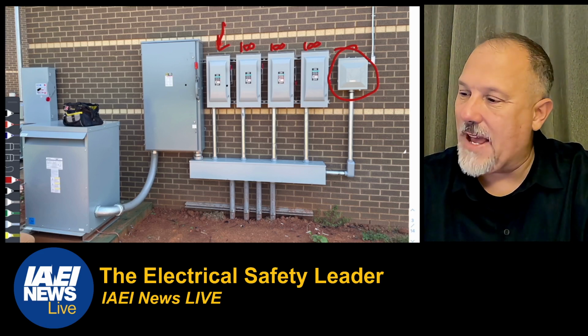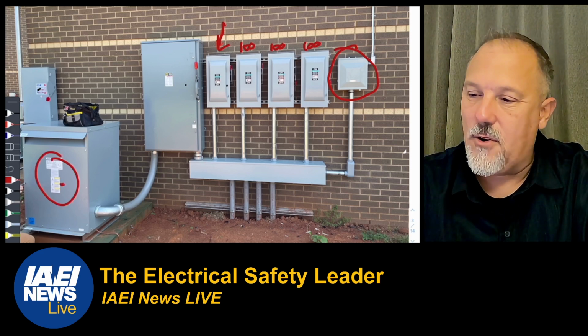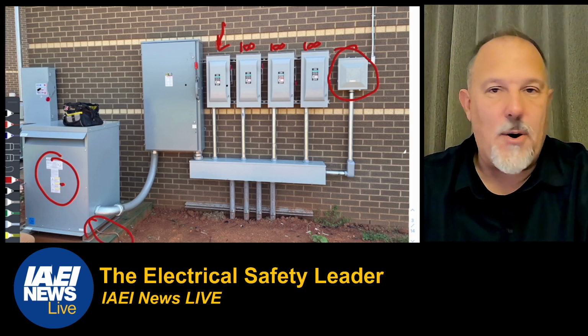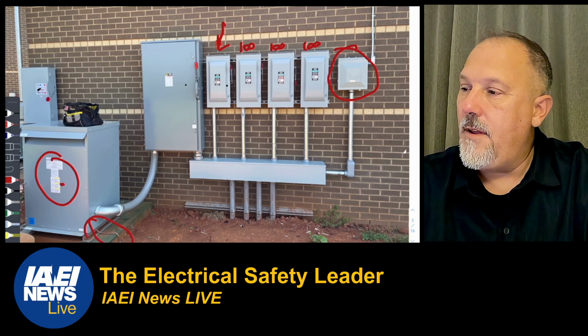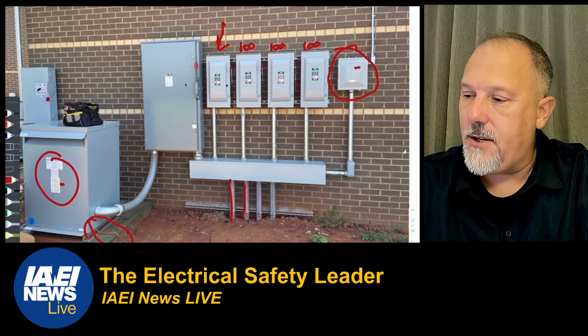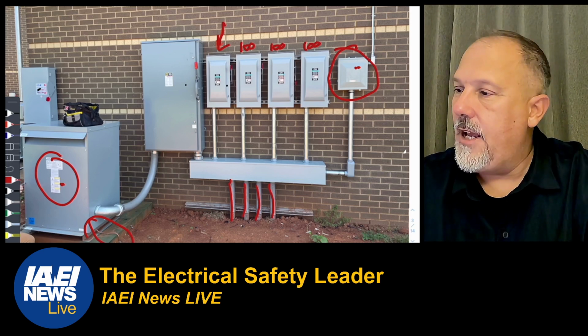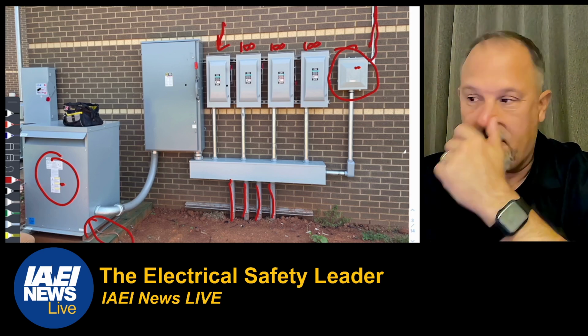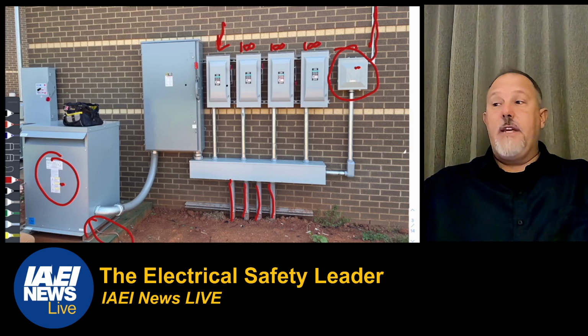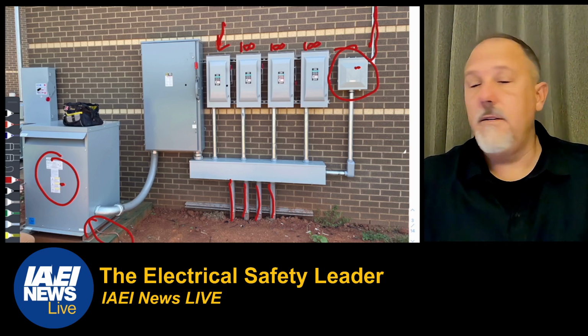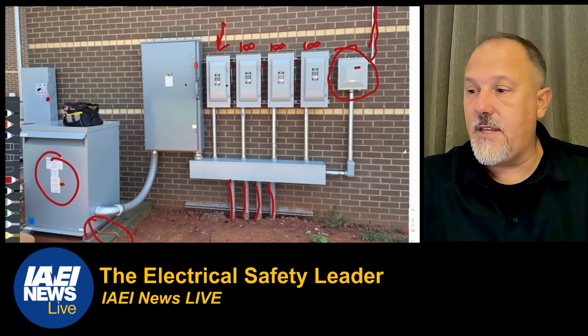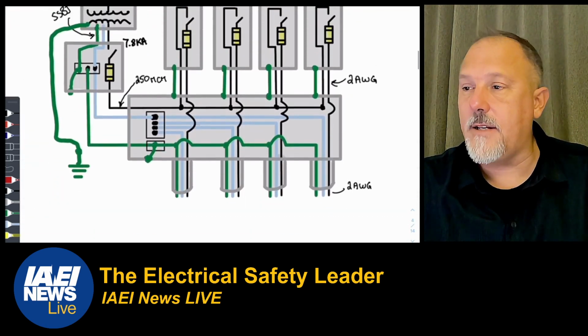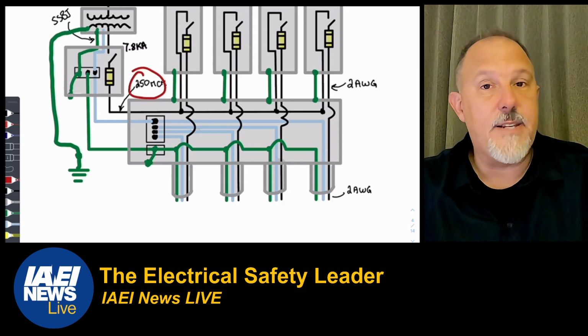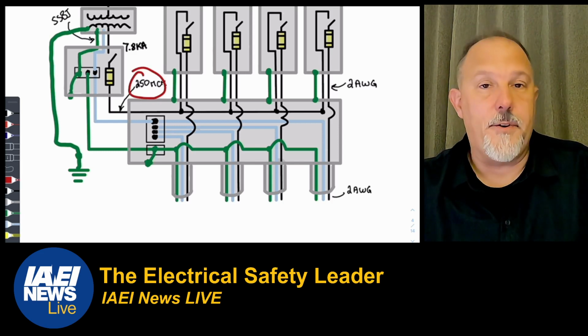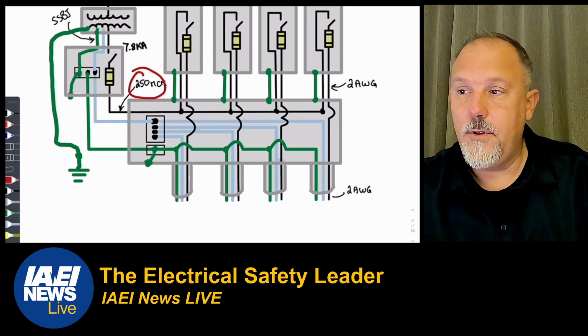I'm waiting on the photo of that, and I'm hoping to get the photo of the inside of that transformer because I want to show the bonding and everything. But anyway, there's another panel board here. So where are my loads? My loads are here, here, here, and here that go to those units, and up here that go to whatever that goes to. So his question was, when they did the load calculation, is that 250 MCM conductor the right size? Should it be a 400? I don't know. Could it be a 400?